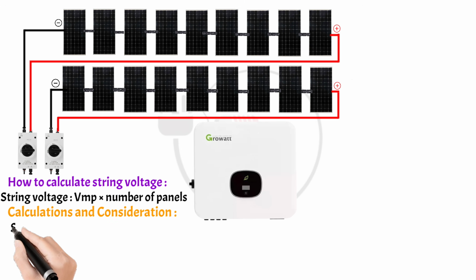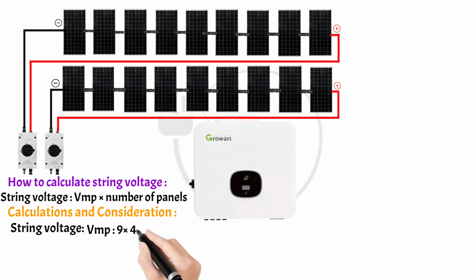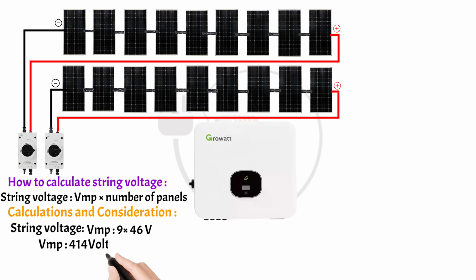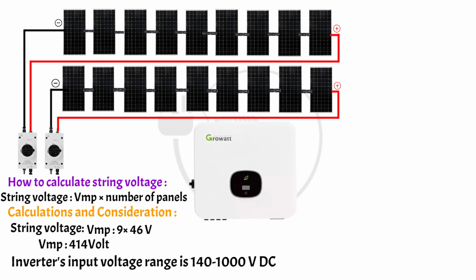Calculations and considerations. String voltage with 9 panels in series. The voltage of each string will be VMP equals 9 multiplied by 46 volt, so VMP equals 414 volt. The inverter's input voltage range is 140 to 1000 volt DC. String voltage of 414 volt is comfortably in this range. Since the inverter has 2 MPPT trackers and you have 2 strings, each string can be connected to a separate MPPT tracker. This is ideal as it allows the inverter to optimize the power output of each string independently, even if they experience different sunlight conditions. Your planned configuration of 2 strings with 9 panels per string is well suited for your 10 kW inverter.